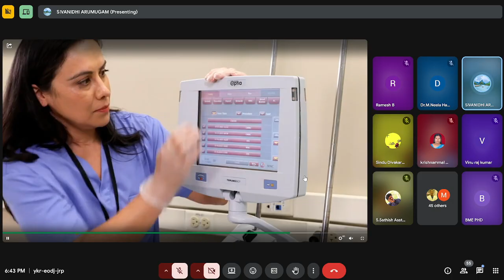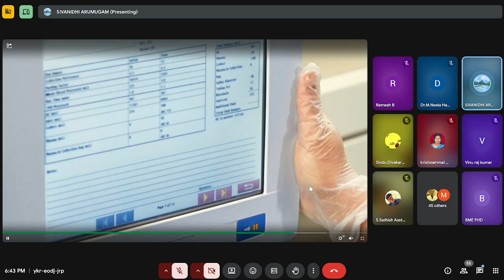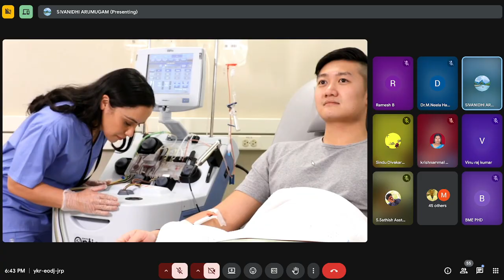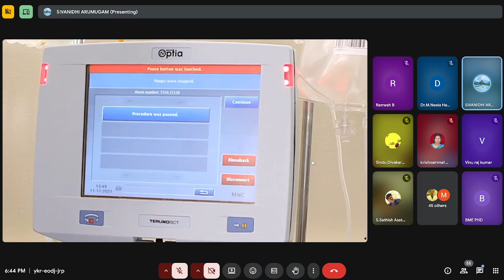And we have one thing called rinse back. For example, in the cassette there may be some blood residuals. To remove that residual, we can use our collected plasma; we collect extra plasma to do the rinse back and flush it. To remove that residual, we call it flush or rinse back. We do that process to remove the remaining residuals and give them back to the donor or to the patient. So that's why we call it one term, rinse back.